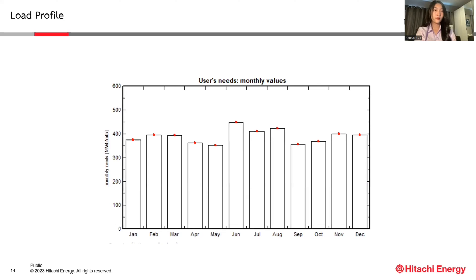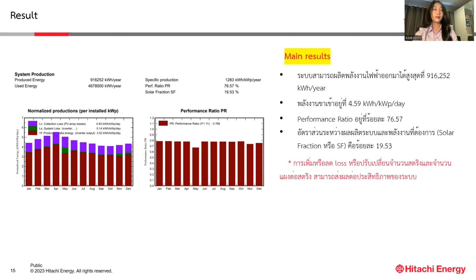After configuring all settings, the program scenarios are graphed to visualize the data. From the analysis, we find that the solar panel system can produce a maximum of around 916,252 kWh per year. The energy input inside the system is 4.59 kWh per kWp, and losses account for 0.14 kWh from the system and 0.93 kWh from the solar panels, resulting in a net energy input of 3.52 kWh per kWp. The performance ratio is approximately 76.57%, slightly below the typical 78% PR benchmark, but a PR of 76% is still considered efficient.